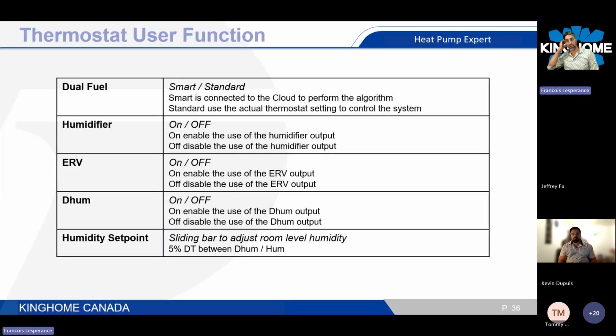Inside the user function, there's a selection called dual fuel. At that point, you can select smart mode or standard mode. Smart mode is only available when Wi-Fi is properly connected and the account on the Kinghome Plus app, which we're going to discuss further in the slides, is properly set up. If it's not on Wi-Fi, then you will have to use standard mode. At that point, you won't use the cloud to perform the algorithm to switch over your balance point from the gas price or electricity price, and you won't have access to the outdoor temperature until you hook up that optional outdoor sensor.